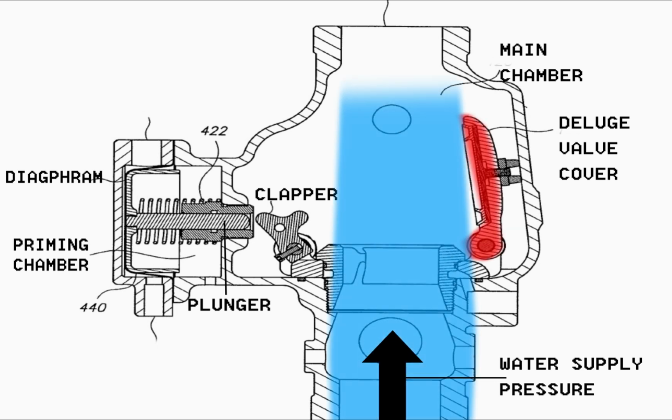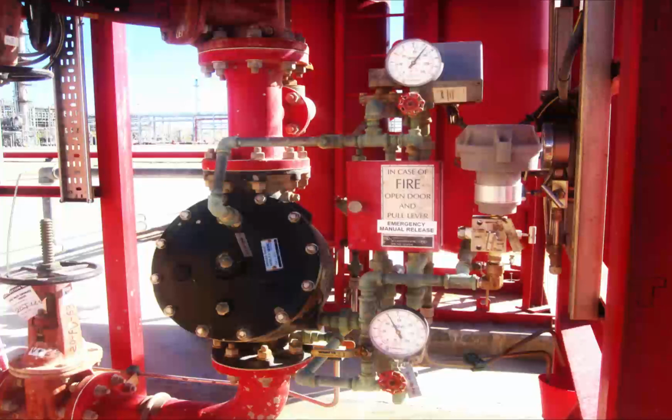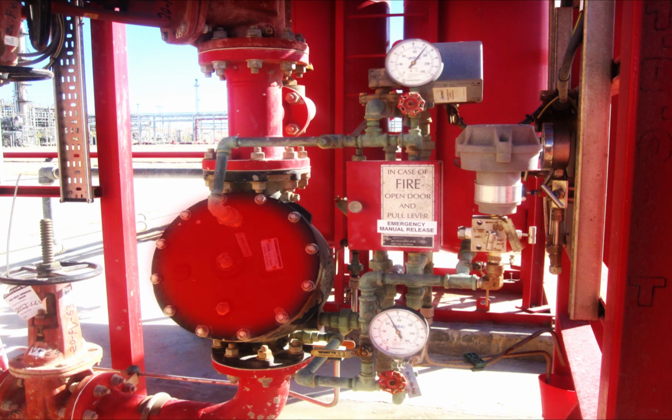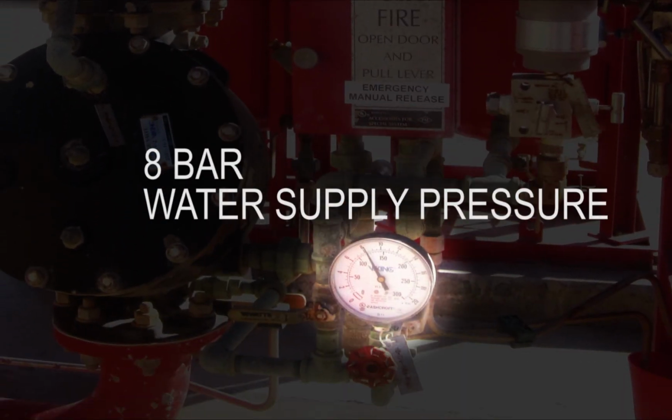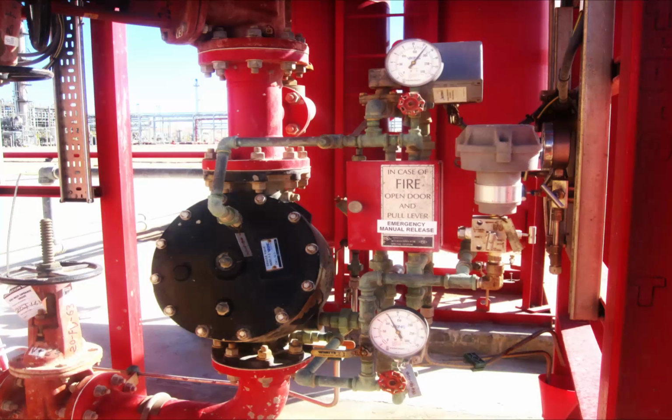the water supply pressure. This photo shows the deluge valve in normally closed position, where the priming water pressure is 12.5 bar while the water supply pressure is 8 bar. The priming water pressure branches from the water supply pressure, so normally there should be a zero differential pressure between them, which is essential for the deluge valve to remain closed.